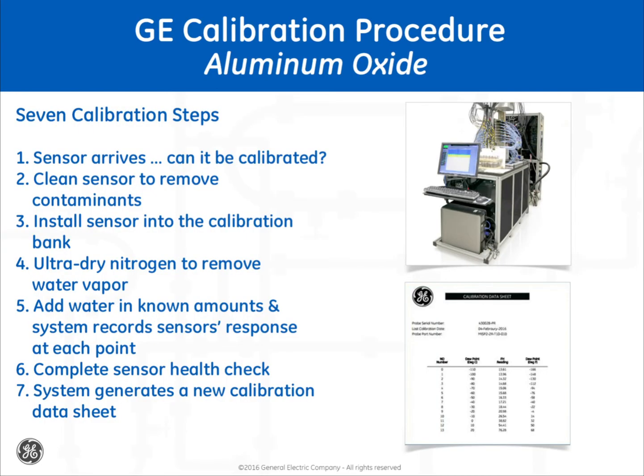At GE, there are 7 steps involved in the calibration of the Panametrics brand aluminum oxide moisture sensors. 1. When the sensor arrives at the service center, the technician checks to see that it's operating. 2. Cleaning the sensor removes contaminants that could impact the calibration and future readings. 3. The lab technician installs the sensor into the calibration system. 4. The calibration system uses ultra-dry nitrogen to remove water vapor from the system and the sensors.